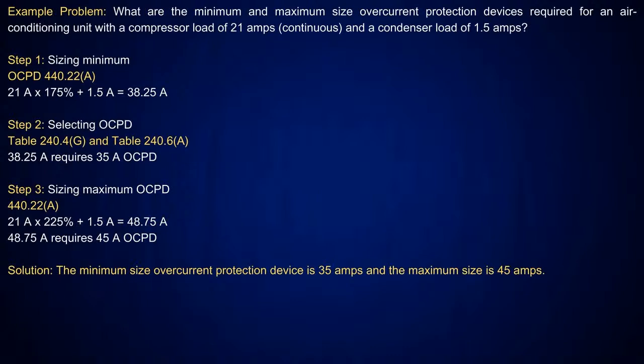But right now they have them as exceptions, like it used to be in 430.52C1. Now, when you pick up 440.22A, it tells you that you're going to be doing a protective device having a rating or setting not exceeding 175%. It says I can't exceed, so that means I'm going to do what? Drop down. Now, what they added in the 2023 is an exception 1 here, and they said without doing any other type of calculation, I'm automatically permitted to go up to the next standard size. And if it still won't start due to the inrush current of that motor, then you've got an exception 2, and it tells me I can take it up to 225%. Well, that's interesting because this looks just like the motor portion now. But I used to come in and look at an AC unit and have a HACR breaker rating there that had a minimum and maximum setting.